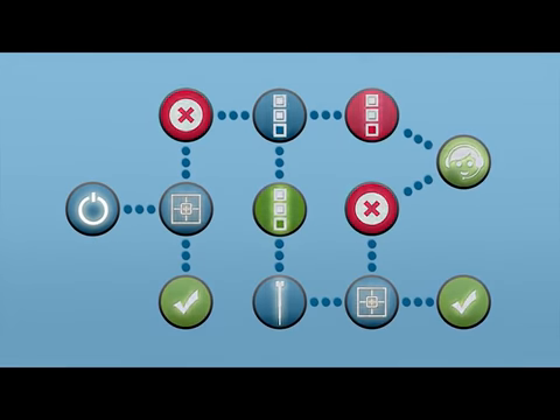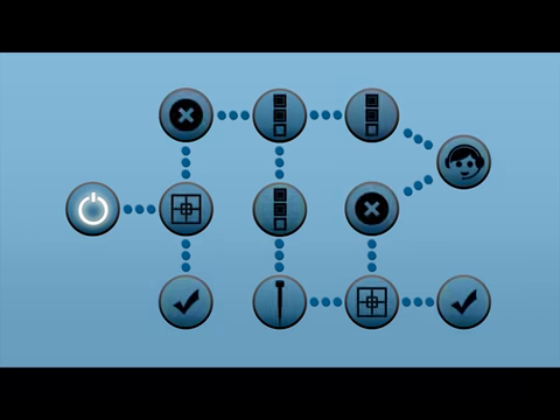Let's review the steps for basic troubleshooting on the MagPix instrument. If you are experiencing issues with your instrument, 1. Run a calibration and verification cycle. If this doesn't work, 2. Run a self-test. If any errors are reported, call technical support. If the self-test passes, 3. Remove the probe, clean it, then replace it and make a height adjustment. Run a system clean. Then, run another calibration and verification cycle to see if the problem is resolved. If not, advanced troubleshooting will be needed by Luminex technical support.